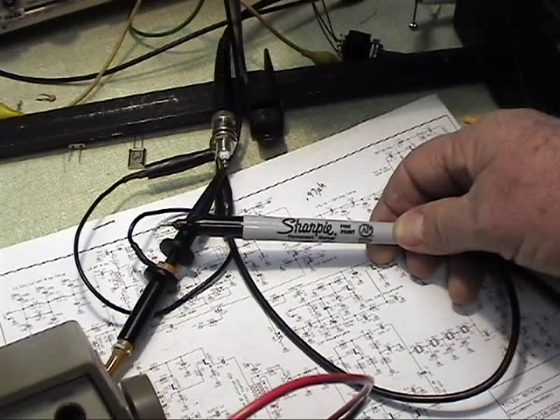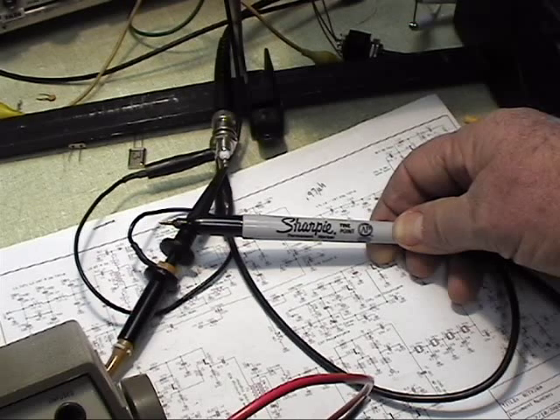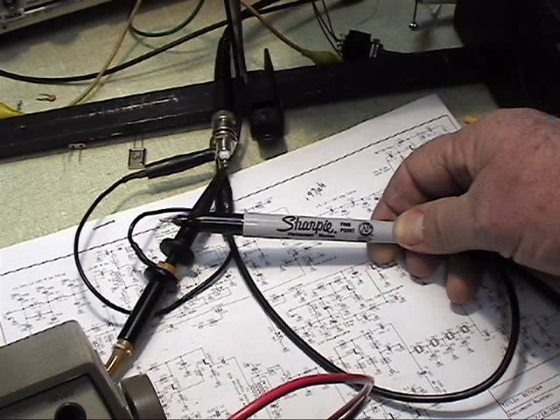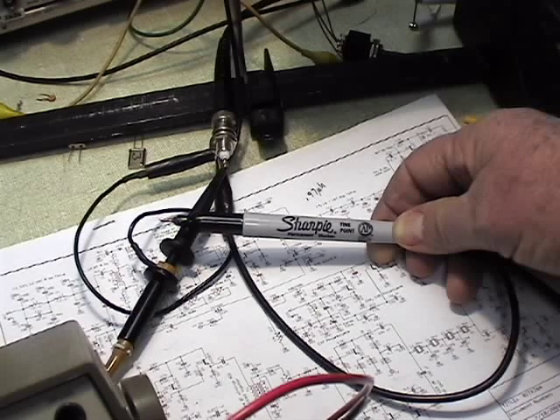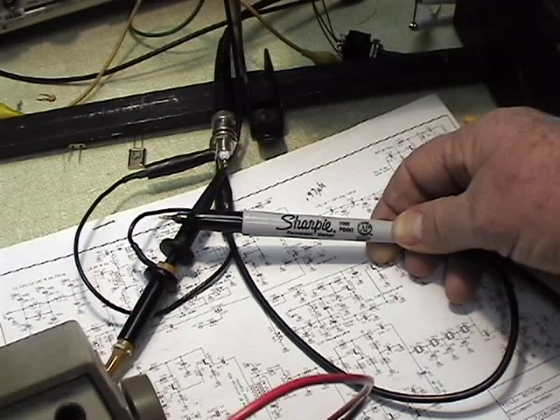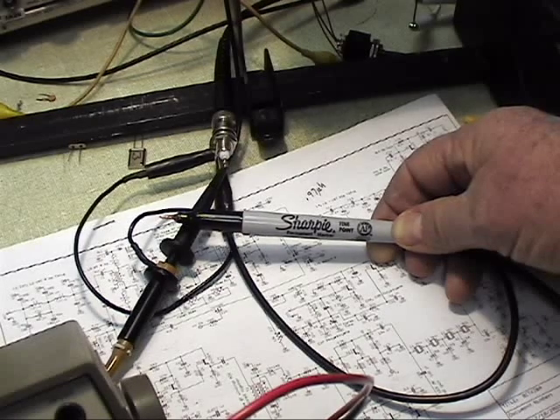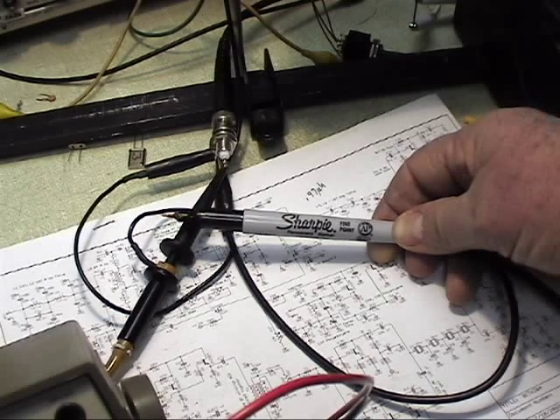With an RF probe, the actual values aren't particularly important. What matters is that you get some value, because there's a diode in the probe causing diode losses, and non-sinusoidal waveforms give different readings since the probe does a peak measurement and converts it to RMS voltage using math. So if it's not a sine wave, it gives wrong answers, and diode conduction gives varying voltages. But if your probe has a DC blocking capacitor in series, measuring any value at all means there's RF present.